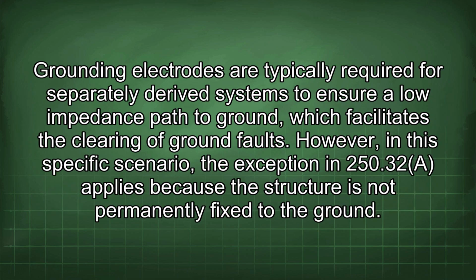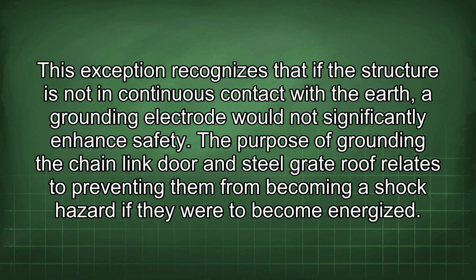Grounding electrodes are typically required for separately derived systems to ensure a low impedance path to ground, which facilitates the clearing of ground faults. However, in this specific scenario, the exception in 250.32 applies because the structure is not permanently fixed to the ground. This exception recognizes that if the structure is not in continuous contact with the earth, a grounding electrode would not significantly enhance safety.